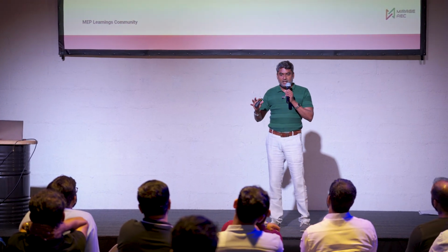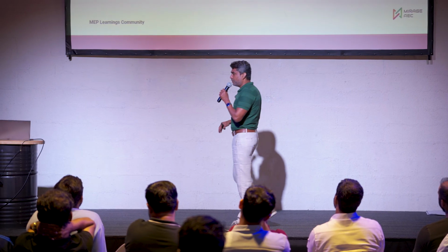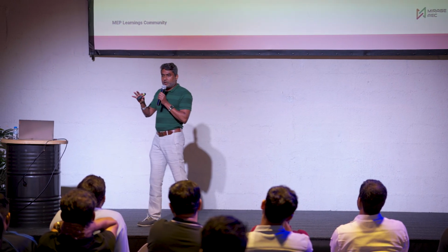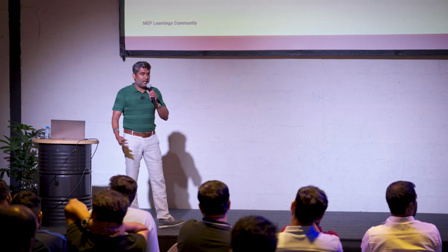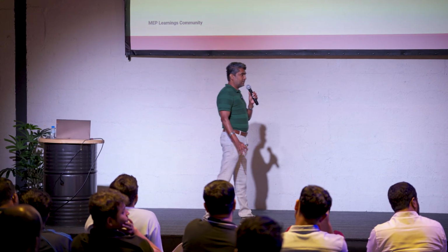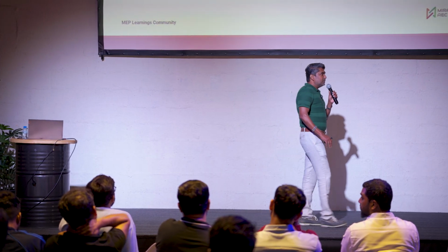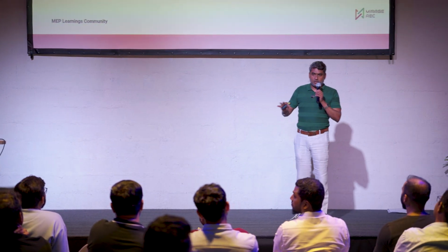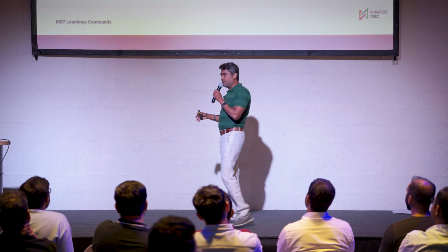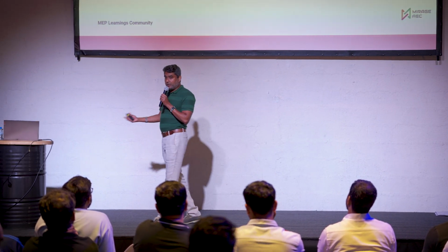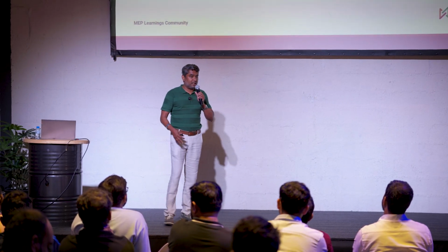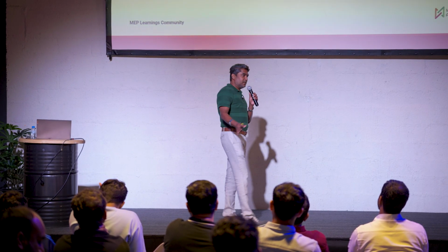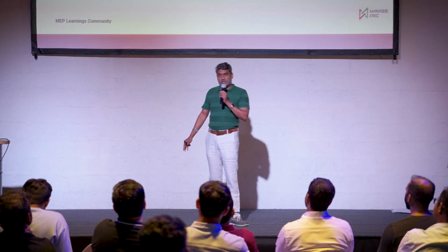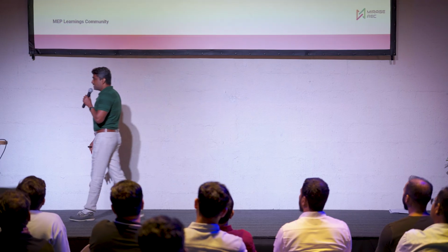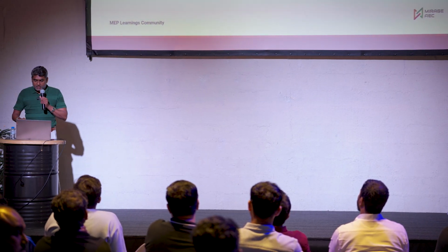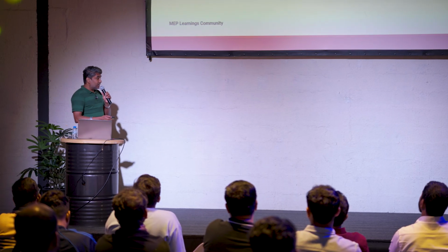It is not just about passing the message to each of the floors and occupants that the building is on fire, or your floor is on fire, you will have to evacuate. That's not the only purpose. The fire alarm system also talks to several other systems, so that it makes sure that when people are alerted, they can safely evacuate the building. That is the most important thing the fire alarm system does, apart from initiating the alarm and notifying the occupants of the building. In the forthcoming slides, we will get to know what all systems it actually talks to and why that is important.